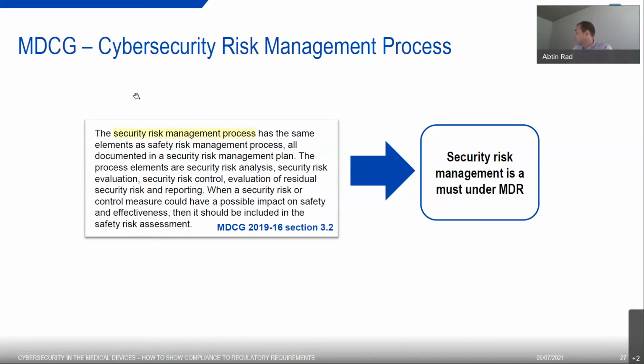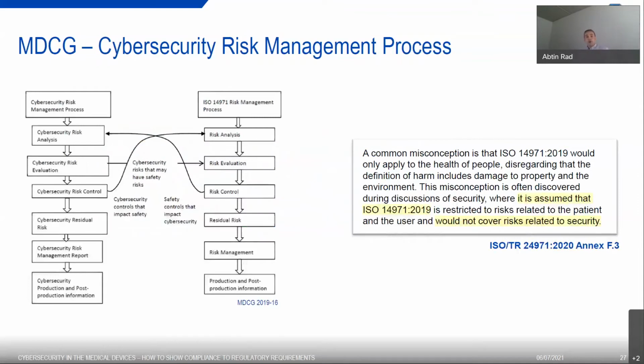So what does it mean actually? The MDCG guidance explains that no separate security risk management process is necessary, and you can implement the security risk management as part of your general safety risk management process, which you definitely have in place already as a medical device manufacturer. But how do you implement cybersecurity in your common risk management process? The guidance explains it in a complicated form, but actually it's quite easy. For each safety risk management step, you need to have one corresponding security risk management step. And this is shown in a graph on the left side of the slide.